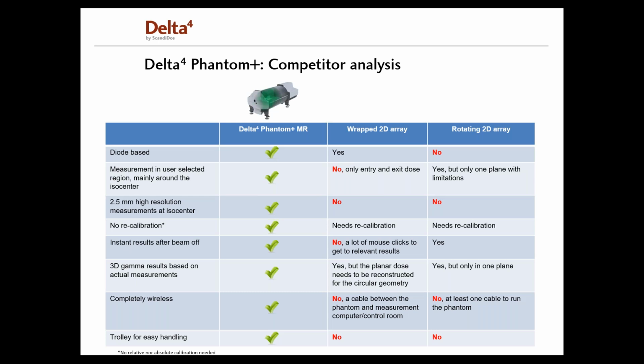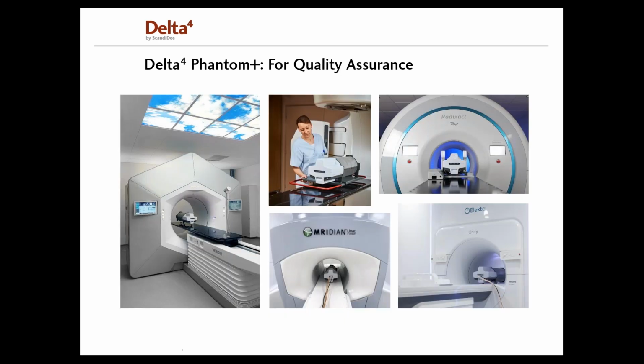With our intuitive and very fast Delta4 software, that my colleague Madeleine will tell you more about shortly, you get instant analysis results as soon as you hit beam off. And due to the configuration of the detector planes, the 3D gamma analysis is based on actual measurements. Our system, as I mentioned earlier, is the only completely wireless system. And also, as I just recently showed you, the Delta4 trolley provides easy and ergonomic handling of the Phantom. And it is, of course, of huge importance, before I finish this presentation, to also mention that the Delta4 Phantom Plus is compatible for quality assurance of all different kinds of treatment techniques delivered by not only all conventional LINACs, but also the Halcyon, the MRIdian, and the TomoTherapy machines.